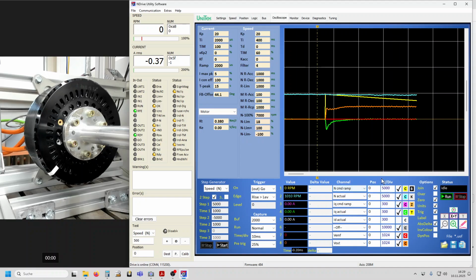For the channels of the oscilloscope, I recommend having the speed command, the actual speed, the IQ current command, the IQ actual value, the ID actual value, and what is very important, the back EMF voltage output and the total voltage output of the inverter. In this case, orange. For demonstration purposes, I have set the KE factor to 0, and you can see the total voltage is provided while the back EMF voltage is set to 0.